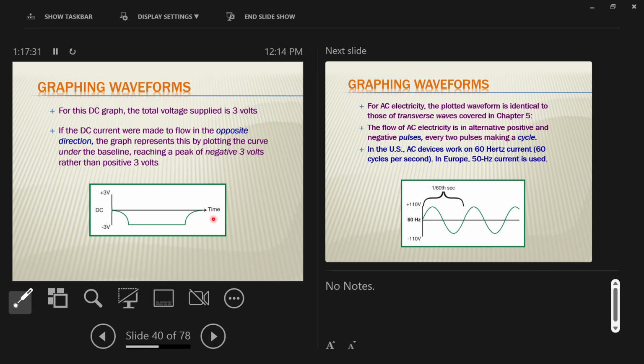Let's look at AC current now. So here's an interesting thing. Your X-ray tube, in order to produce X-rays, the actual X-ray tube part of it, the light bulb type part of the tube that does the X-ray making, has to use direct current, okay? But your X-ray machines plug into the wall and have to access alternating current. So we're given alternating current for free, right? We get it from the wall, and then we'll have to do something to the alternating current to make it look like DC current, because our X-ray tube needs DC current. We'll explain why later. I'm not going to get to that part today.